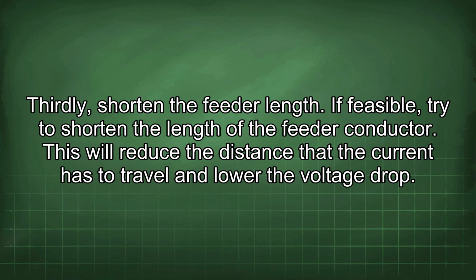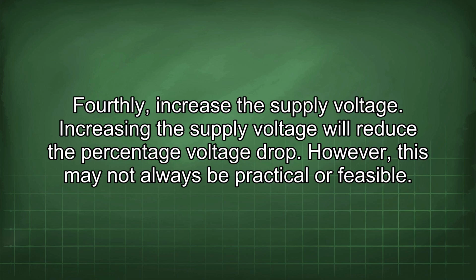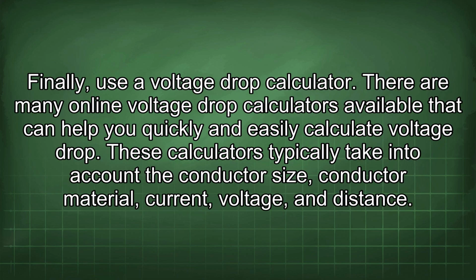Thirdly, shorten the feeder length. If feasible, try to shorten the length of the feeder conductor. This will reduce the distance that the current has to travel and lower the voltage drop. Fourthly, increase the supply voltage. Increasing the supply voltage will reduce the percentage voltage drop. However, this may not always be practical or feasible. Finally, use a voltage drop calculator. There are many online voltage drop calculators available that can help you quickly and easily calculate voltage drop. These calculators typically take into account the conductor size, conductor material, current, voltage, and distance.